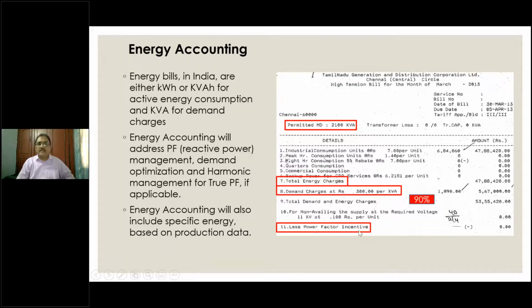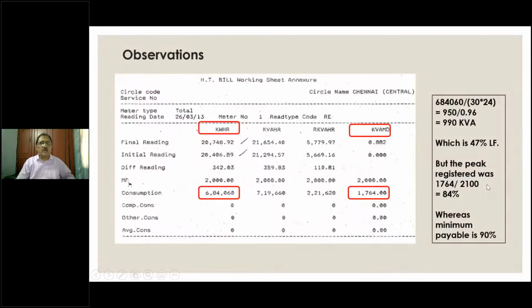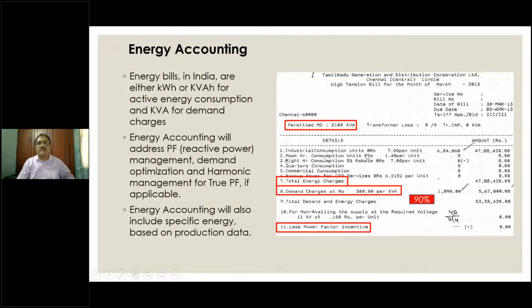This is one. And there was no power factor incentive even at that time. You can find zero here. Today also there is no power factor incentive, but penalty is there for power factor, both lagging power factor as well as leading power factor. I'm sure Maharashtra also has lagging power factor and leading power factor. Both will be penalized. Penalty will be levied by the electricity bill. And total energy charges are, as you can see here, approximately 6,84,000 units, and it is being paid on this basis: 7 rupees per unit during normal time, 1 rupee 40 paisa during the peak hour time, differential tariff, 5% rebate during the night hours. So this is the power bill, what it reveals.